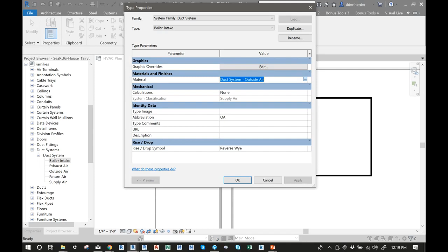If you want it to show shaded or look like a gray duct no matter what view you're in, you have to apply a material to it, otherwise it will use the default material out of the box, which is just basic gray, and all your ducts, no matter what system they are, will look gray. However, they will have an outline of whatever color they are assigned. So in a shaded view, you'll see gray with blue or red outlines. But if you want the entire duct to be red or blue or gray, you need to do a material override.